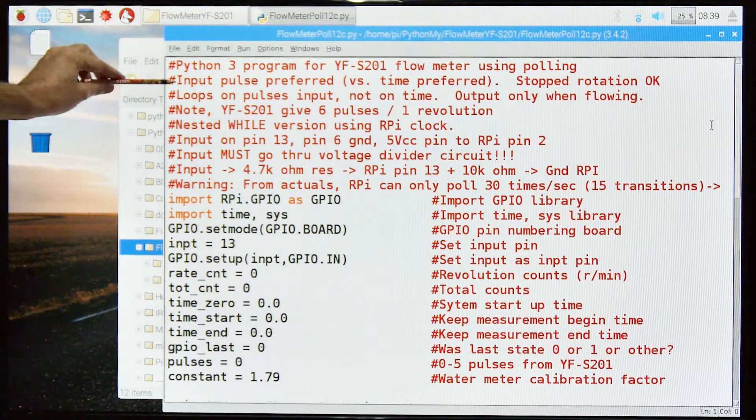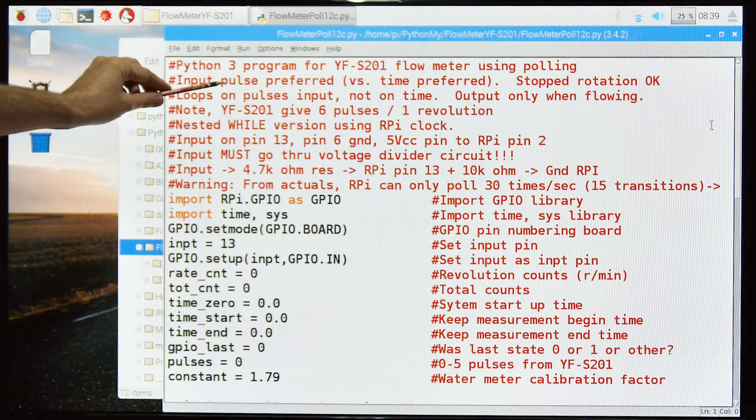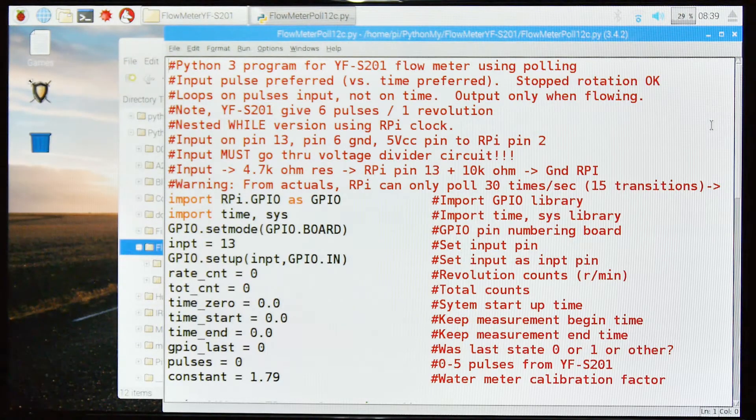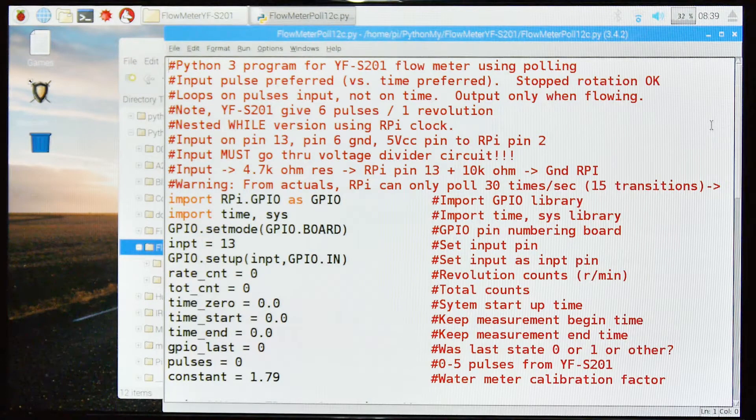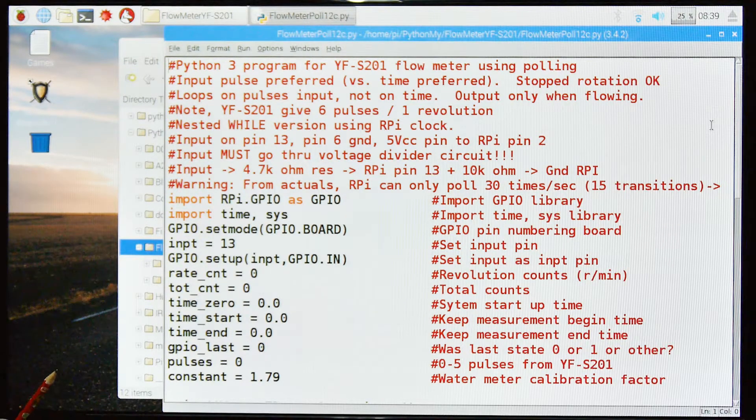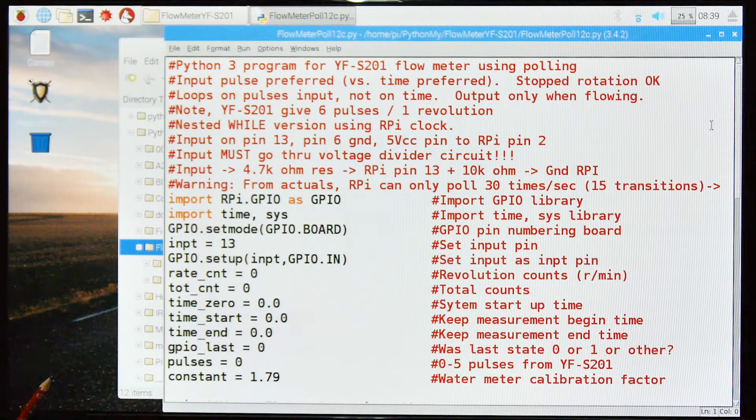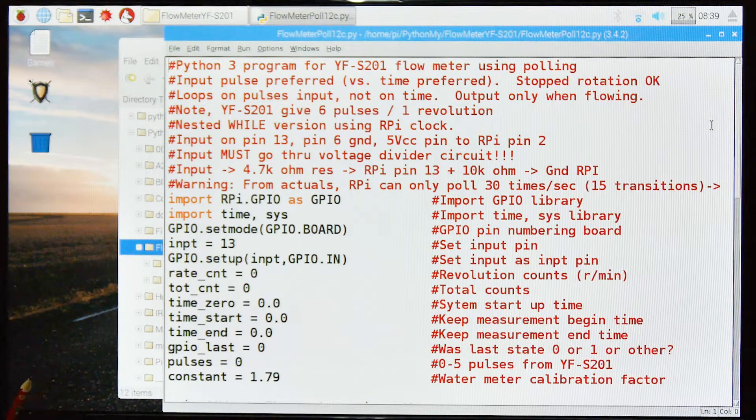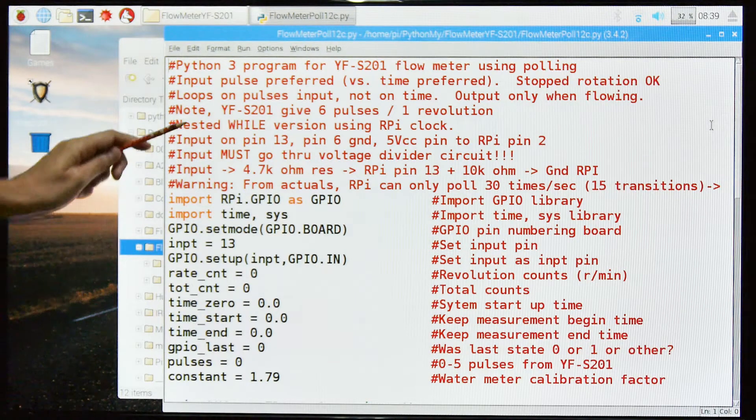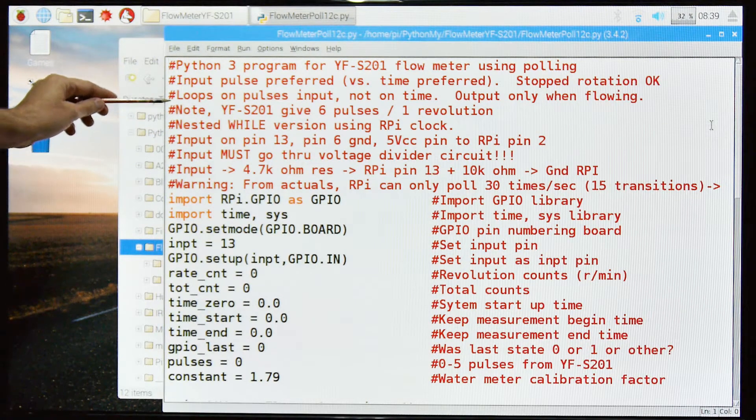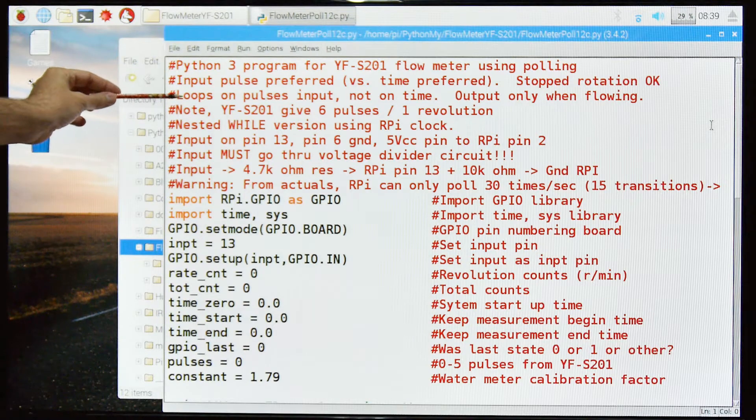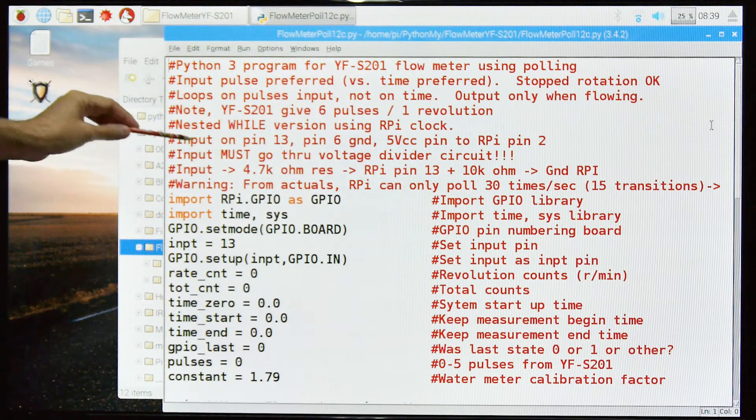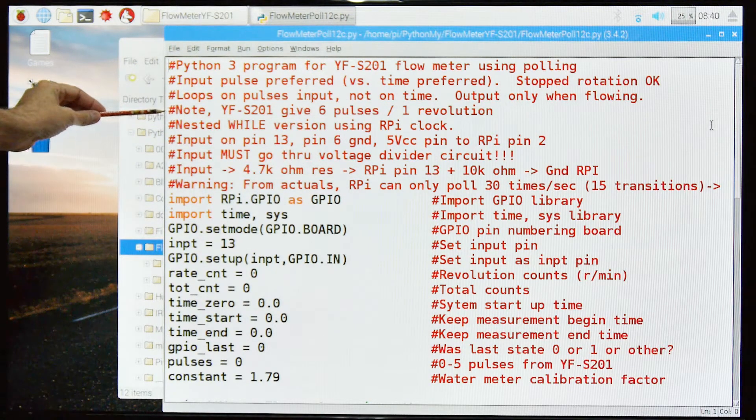This is input pulse preferred. In other words, it acts only when the impeller is sending pulses. It's not based on time. So it doesn't give a reading every 10 seconds, it gives readings when the impeller is turning. In other words, there's output only when it's flowing, when the water is flowing.